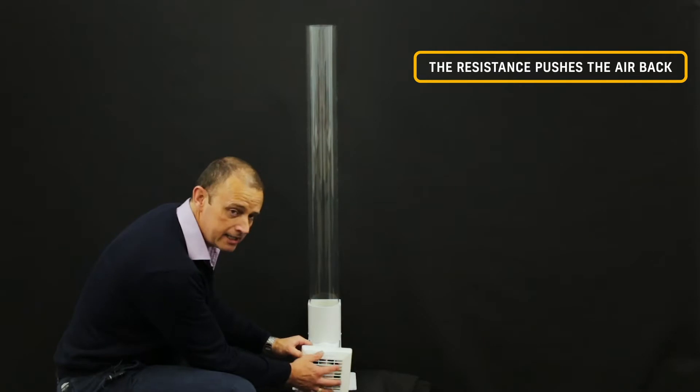Got one more here. So again, this fan, a little bit bigger, a little bit wider. But again, you'll see with this fan it just can't cope with that resistance on the system. So what you've got here, because the ball's not moving up, the air is actually coming back out of the fans.